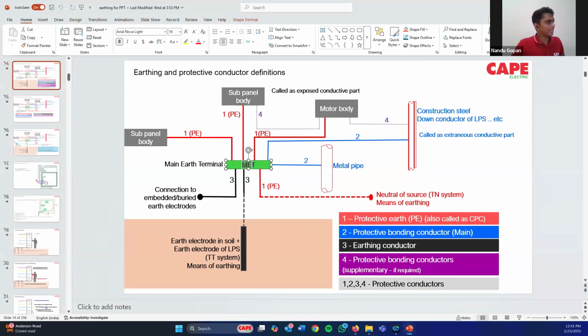So MET is not a big term - MET just means a metal strip. You take a metal strip, and if there is a sub panel body, you connect that strip with a wire to the MET. If there is some down conductor, you connect it again with a strip and a wire. If there is a metal pipe, you connect it to the strip. Everything should be bonded, that's it. You just need a wire and connect everything together to a strip. That's it, it's not a complicated thing.